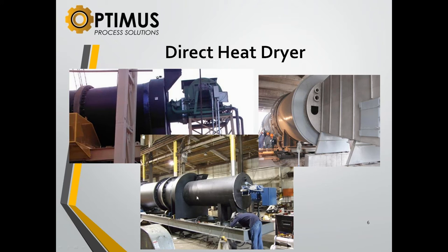So in this one you've got a combustion chamber over here. Can you expand a little bit more? Yeah, we have this portion right here. We have a combustion chamber on this dryer. We have a burner that's bringing the combustion gases into this mixing chamber or combustion chamber. We have a portion where we're allowing air. We're actually force drafting air to come in to move around a thimble there, and then mix after combustion. It mixes with the hot gases so that we can bring the air temperature that we want into this dryer. That would be lowered. That particular dryer was both inorganic and organic materials mixed, and we had to temper the air on account of the organic materials.